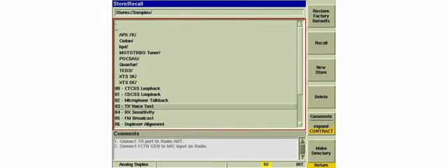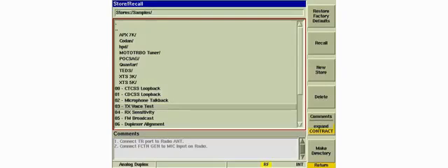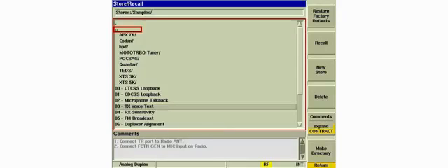The transmit voice test sample has been modified with different generate and receive frequencies. When saving setups, never overwrite a sample with new settings. The samples are a part of the instrument's system. The next time the instrument is rebooted, the new stored settings would be overwritten by the system. Thus, make it a practice to only store setups in the root directory under stores or in a directory you have created.